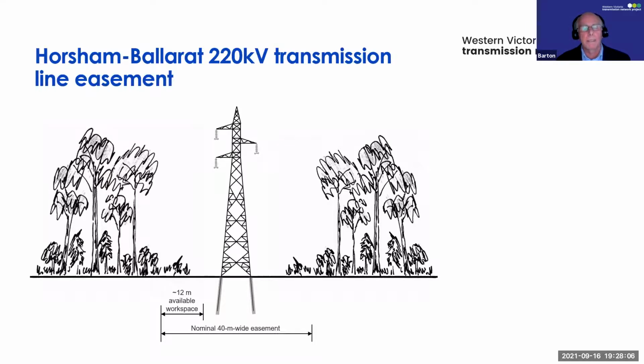That photo was taken just at the back of Ballarat. That transmission line sits in a 40 metre wide easement. The foundations for the tower go some 8 to 10 metres underground, and around that tower is an earth grid. Taking that into consideration, we have about 12 metres of available workspace, which is highly constrained both from a safe workspace and a physical space perspective to install infrastructure.